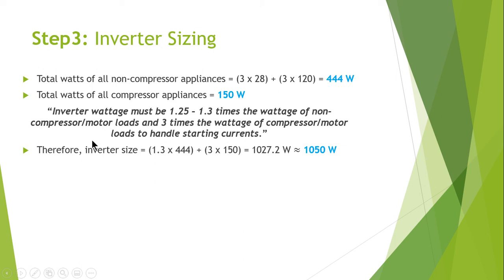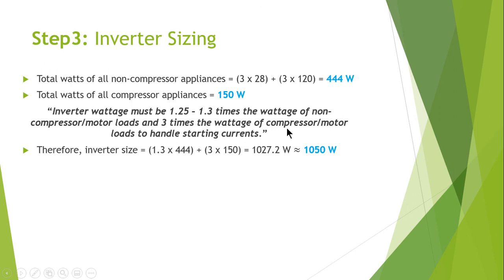Therefore, the inverter size is: 1.3 × 444 watts (non-compressor appliances) plus 3 × 150 watts (compressor/refrigerator), giving a sum of 1,027.2 watts. For ease of design, we select an inverter of approximately 1,050 watts.